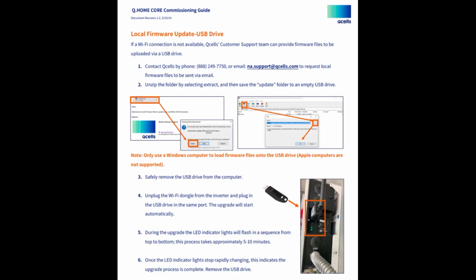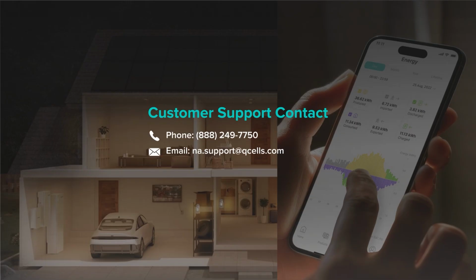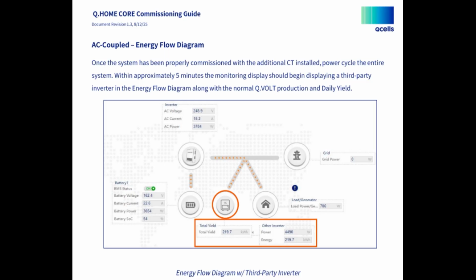The steps outlined for the firmware update require the inverter to be connected to a network. If no network is available for the inverter to connect to, a local firmware update can be pushed using a USB thumb drive. Please contact support for more information on where to access these files. After resetting the system, the inverters will enter an automatic check mode. Once complete, confirm no errors or alarms are flagging on the system.